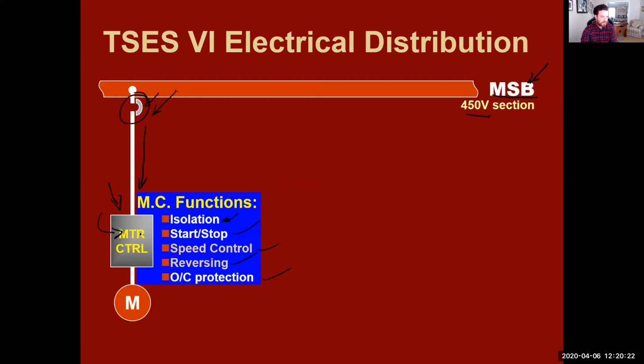If you would have to work inside of this motor controller, then that would be isolation. But what about your start and stop? If you have a start and stop button and there's a short in it, do you want 440 or 450 volts going through it? You could get electrocuted just by pressing that start button. That would hurt. A lot.